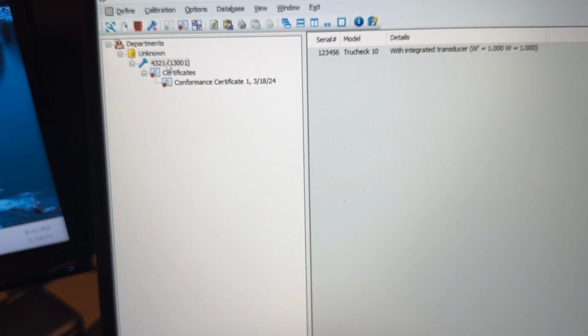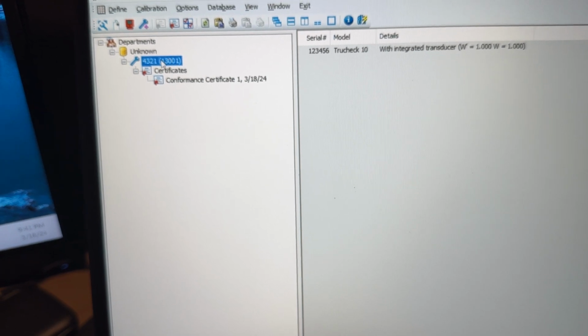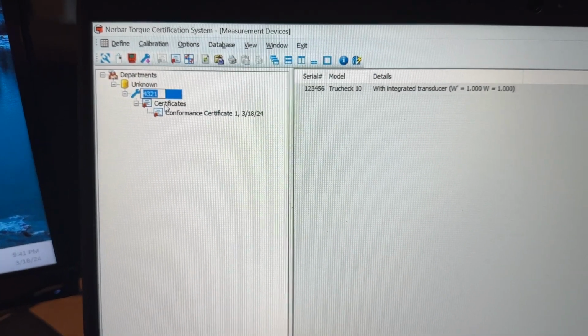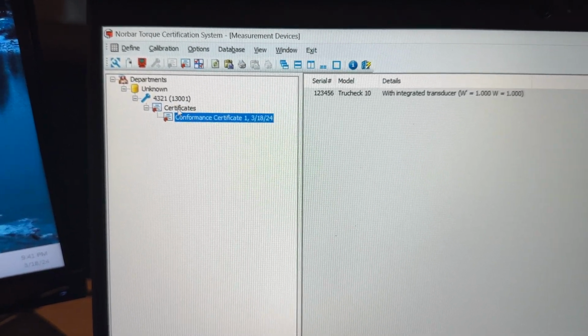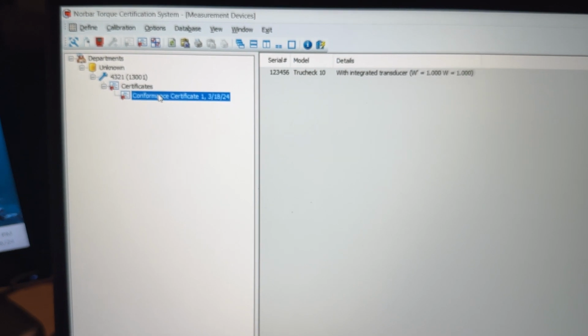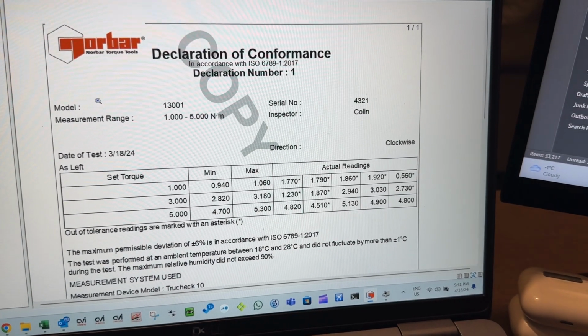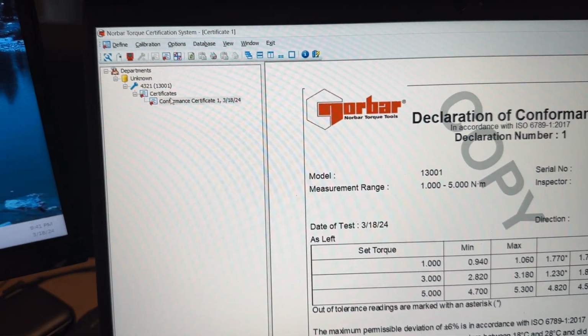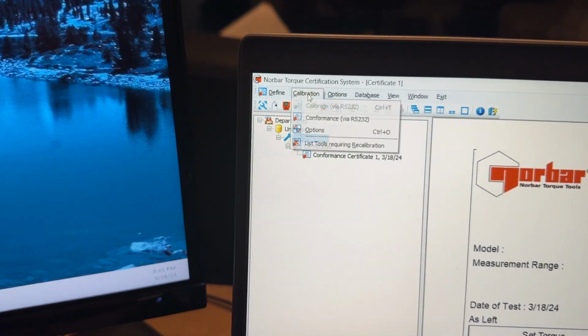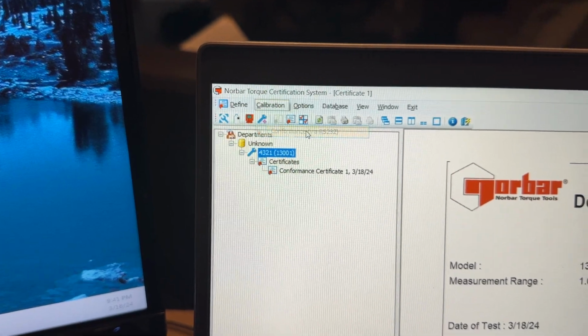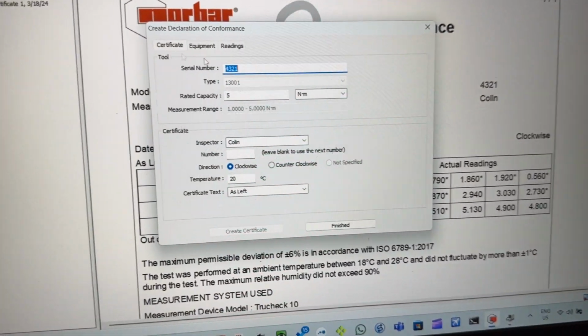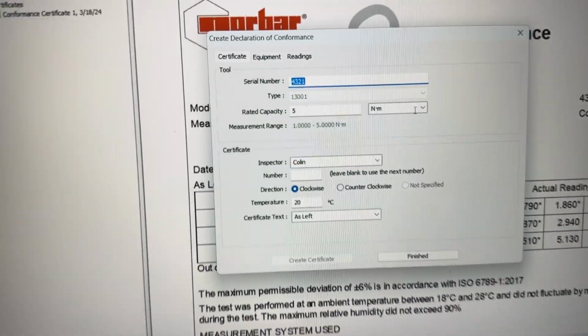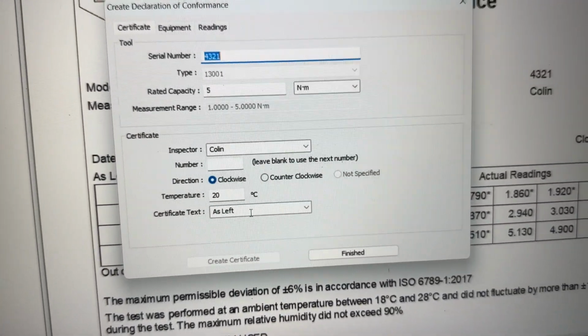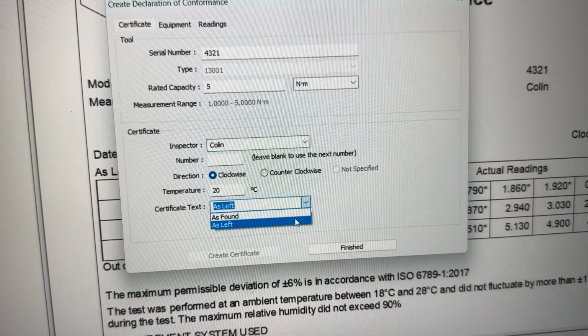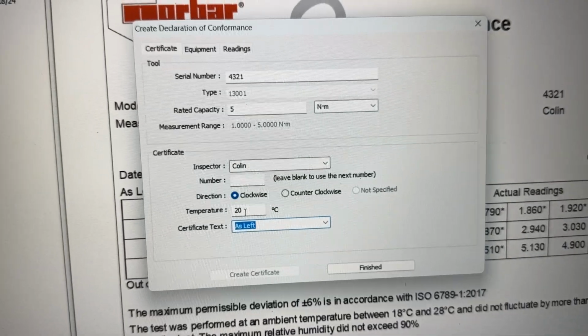If I go down here, this is one tool within our database that I have in there, and I can go back and look at the previous certificates I did or conformances, or I can, let's see if I can open this. So yeah, I can look at the previous. It's showing me it's a copy right now because I've already opened it and printed it. But if I want to go back to the tool and do a new calibration, actually the model I picked won't let me do a calibration. It says it wants to do a conformancy, which is similar. So I got my information here, serial number, rated capacities, 5 newton meters of the tool model that I selected. And I want to do as left or as found. It's just going to leave that text on the cert, clockwise, counterclockwise, room temperature.